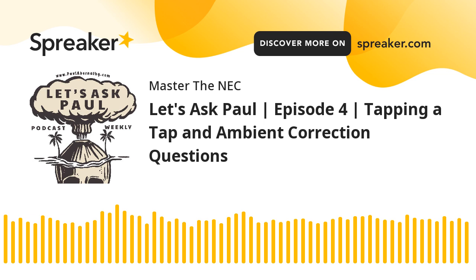Remember that 0.87 was the ambient correction at 108 degrees Fahrenheit. So I take that 28 and I divide that by 0.87. And that is 32.18. So I have to have a conductor that is good for 32.18 amperes. Now I'm going to go to the 90 degree column because remember what it said in 310.15(A) that I can use the 90 if I'm doing adjustments or corrections. Well, I am. I'm doing an ambient correction. So I'm going to search for a conductor under this 90 degree column that is good for 32.18.